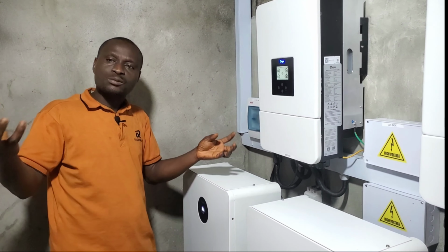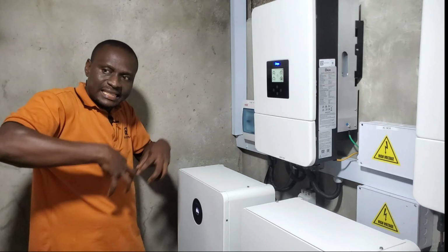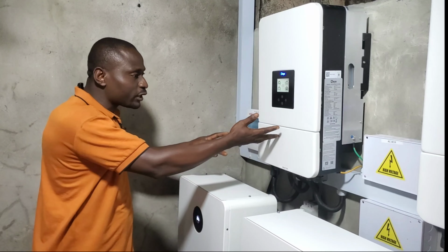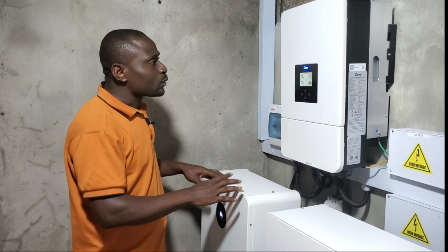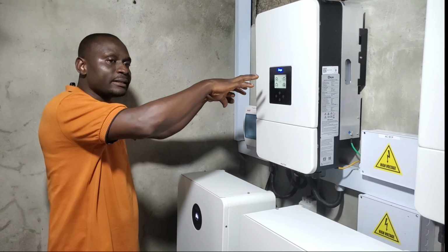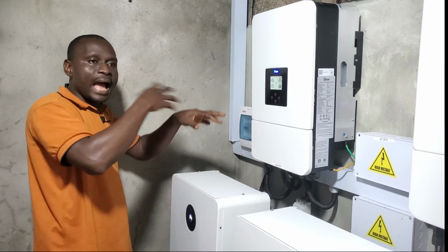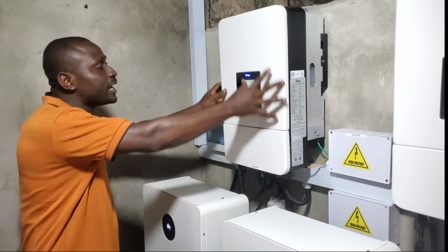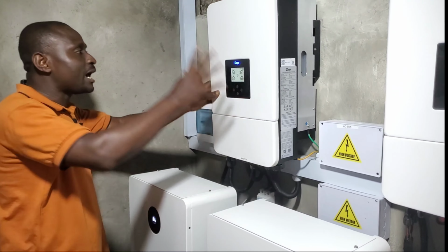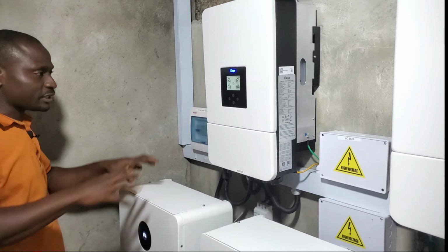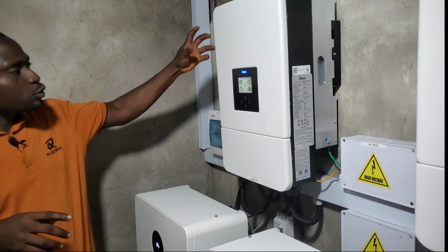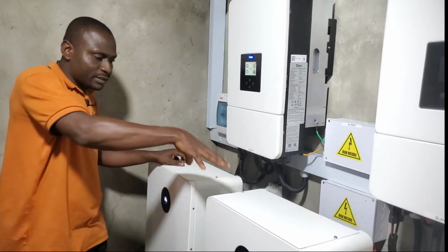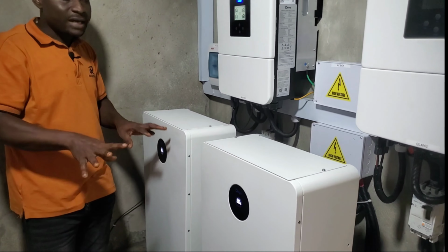Hybrid inverters na inverters wey get solar charge controller inside, and you fit use NEPA, you fit use generator to connect for here and e go still power your loads. So the charge controller wey dey inside the inverter, e fit be MPPT or e fit be PWM. But the one wey dey here, because this one na good inverter, na MPPT solar charge controller. So when the thing come from solar panel, the solar charge controller go collect that power, hold am, control am, send am to battery to charge your battery very well.